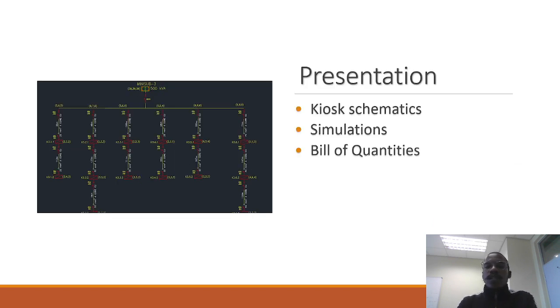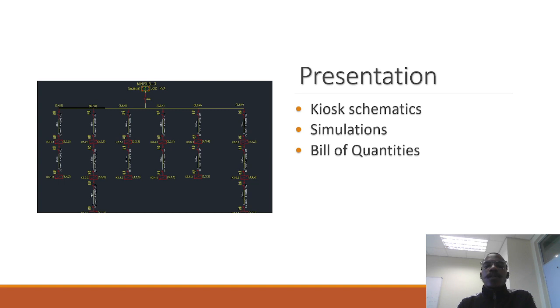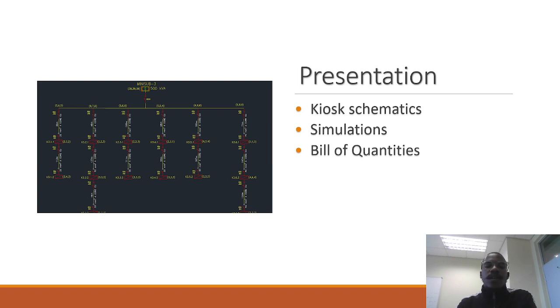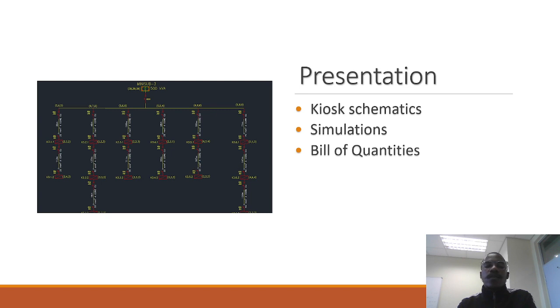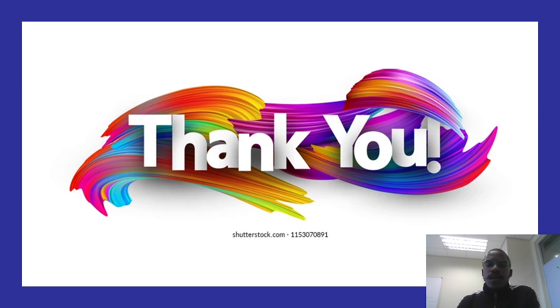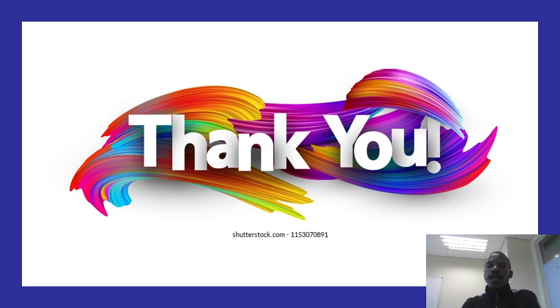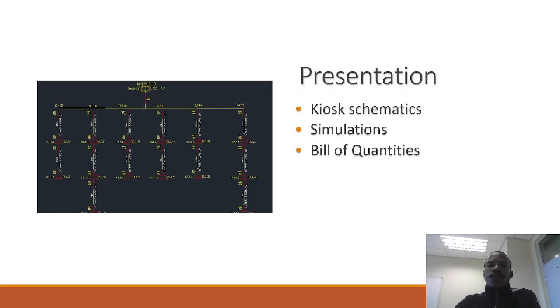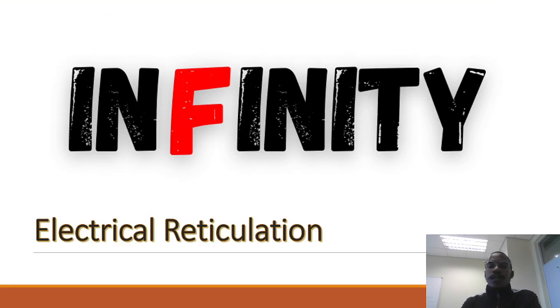For the presentation, we look at the AutoCAD drawing as to how you have done your reticulation. Does it make sense? Are your kiosks numbered properly? Then you're also going to do kiosk schematics. The image you see there is Miniature Sub 3 that I designed. It's a 500 kVA miniature sub with different kiosks connected to it, how many houses it's supplying, and the phase balancing, basically how many houses are connected to the red, blue and yellow phases respectively. That is it for the first introduction to the video on reticulation. I will take you through another video as to how I did the reticulation for a suburb in Windhoek and explain it bluntly. Thank you.